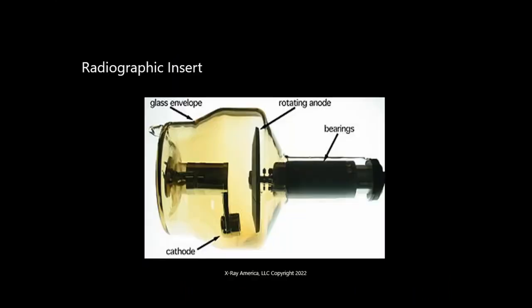Okay. So refer to the glass envelope. In the glass envelope, this is all in a vacuum. So we have what we refer to as a rotating anode. This is referred to as a target. This whole assembly is referred to as a rotating anode. These are bearings. And you have a cathode head. This is all the cathode.